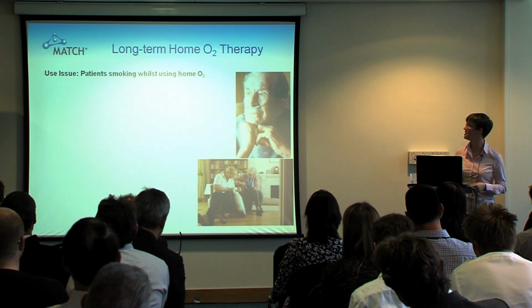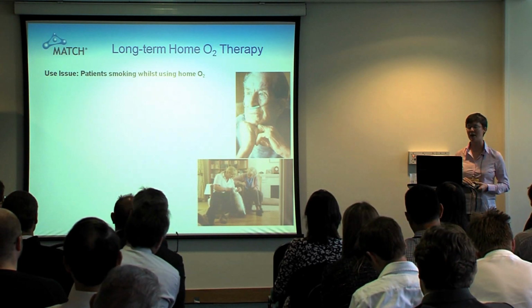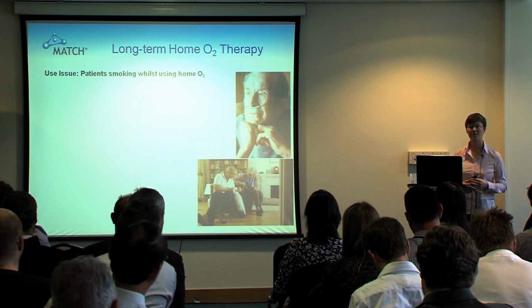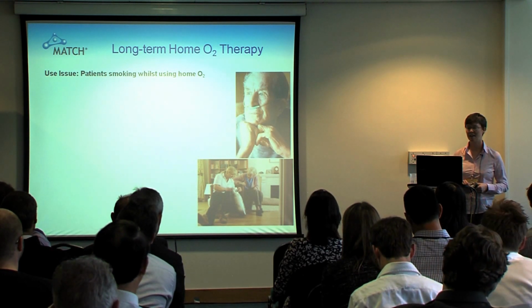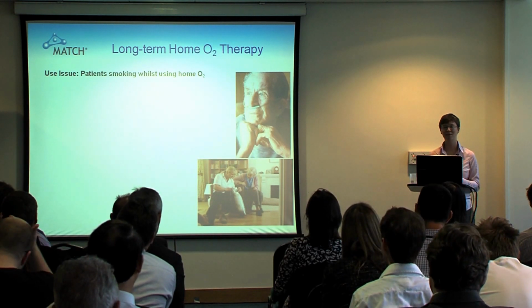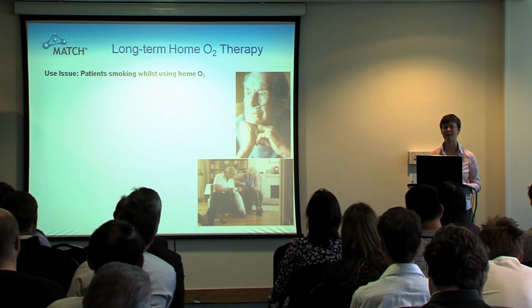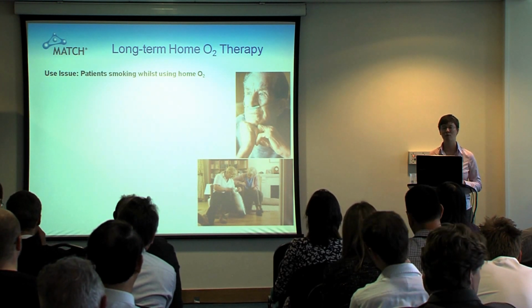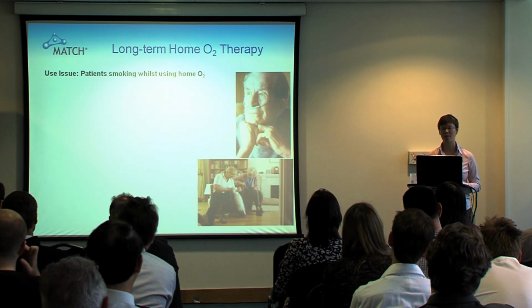This incident was one that really piqued my interest in the whole idea of home healthcare. When I was working at the NPSA, every week we would review all the ways that people had been killed and severely harmed in the healthcare sector, which was absolutely fascinating and terrifying at the same time. I was struck by how little information we got from incidents that happened in the home, and it was very much only when things went very badly wrong. This was something that happened at least a few times a month, where we would get reports of severe burns for people smoking while using home oxygen therapy.